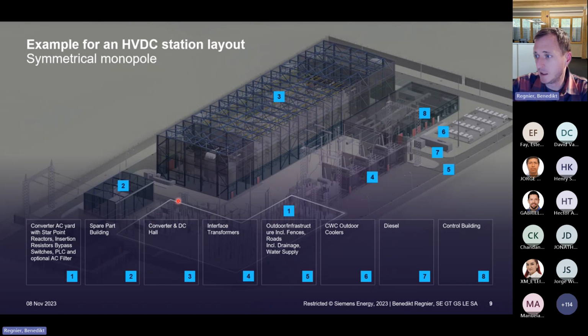Here you can also see some small filters. This is not always necessary, because the big feature of the VSC is that it doesn't really produce any harmonics, but it may amplify harmonics which are already there in the grid, and then we need to filter those out. Or, in the high frequency range, there might be PLC radio interference for which we need to consider limits. Then we also need some high frequency filters to not disturb the existing infrastructure close by.